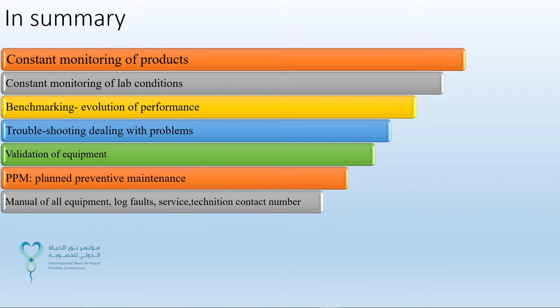manual of all equipment, log faults, service technician and technician contact number, calibration of external measuring equipment, annual maintenance, contacts of equipment and filters with the supplier company, daily control of temperature and CO2 and pH. Especially the last point, it's very important to be checked every day. Stable culture condition.